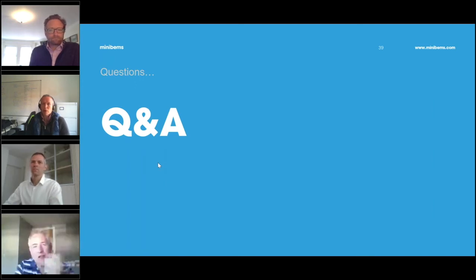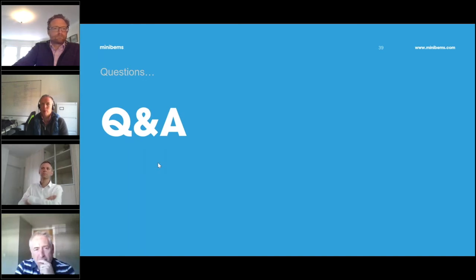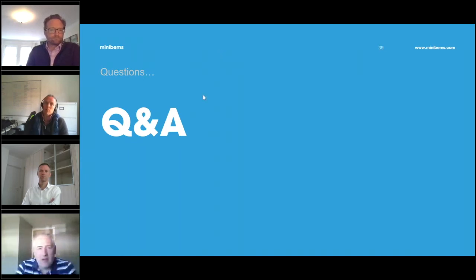No, I agree, Dave. I suppose my question was more on the ambient. I was still on the ambient thing. If you work on the basis that you're going to need, at least from a peak load design point of view, those high flow temperatures for peak loads, is using 1,000 heat pumps, as you say, feasible? Given that, do you get a different kind of characteristic COP out of the smaller type of unit with different refrigerants and different technology than you do out of your large scale, ammonia-based heat pump at those temperatures?